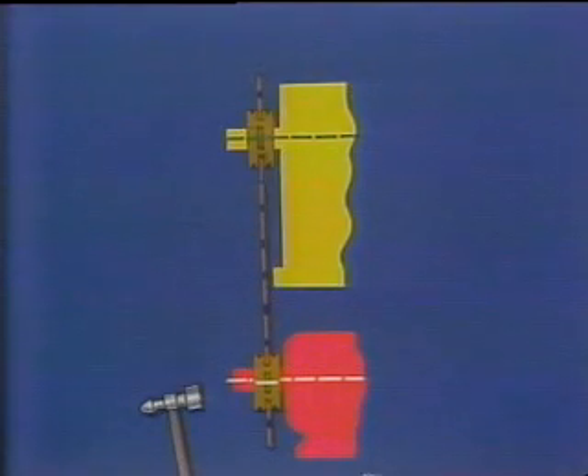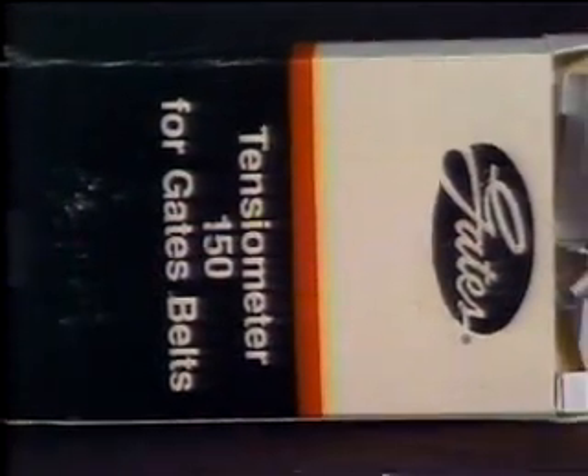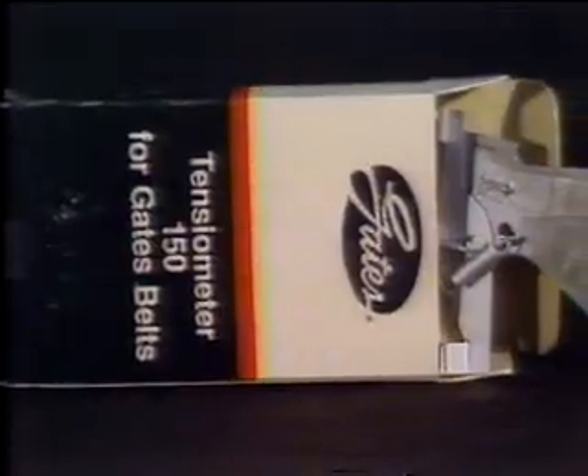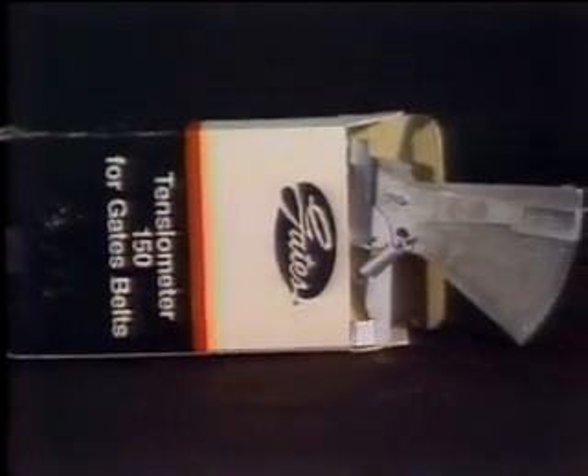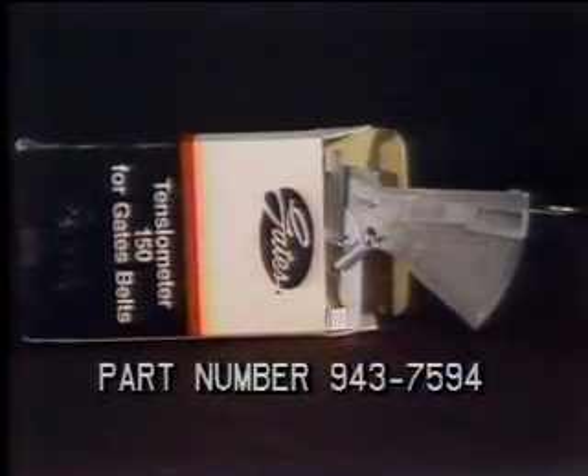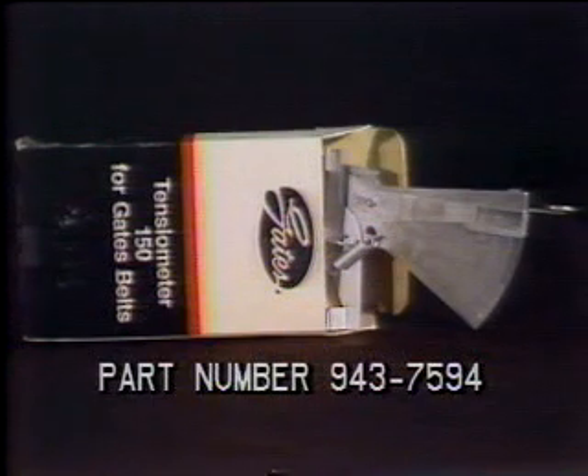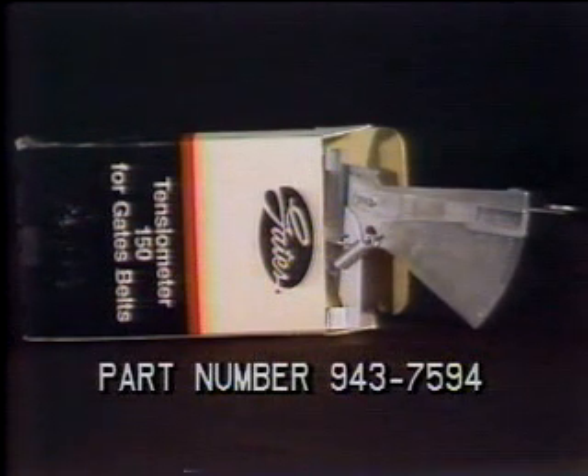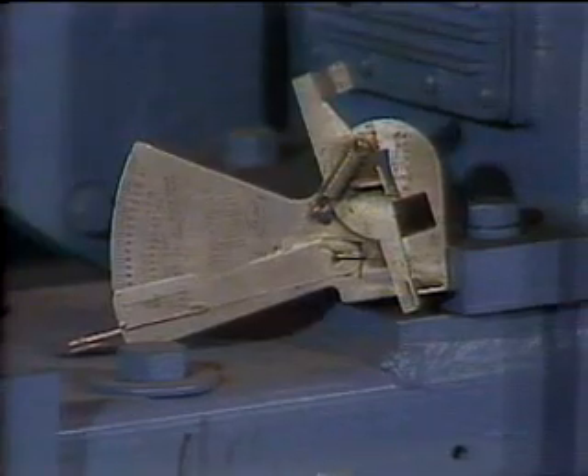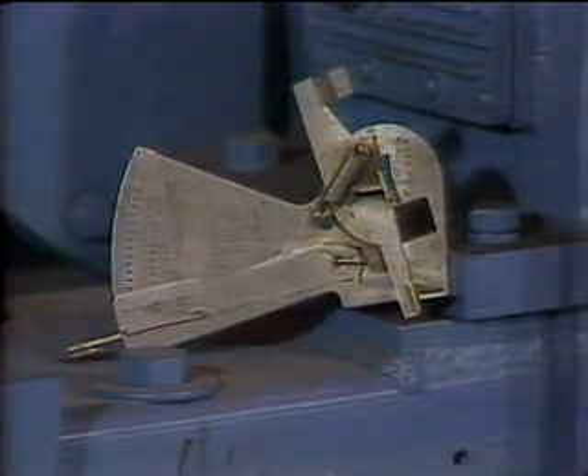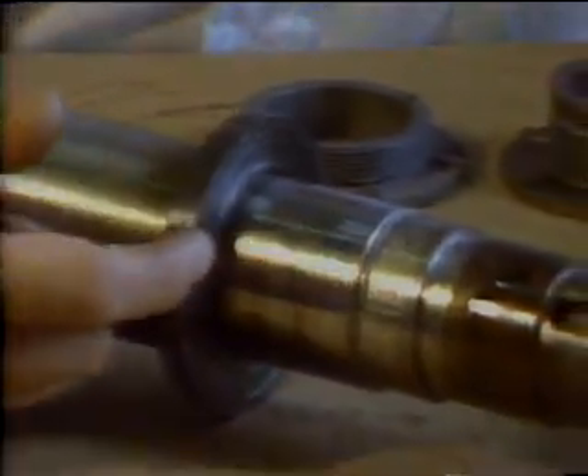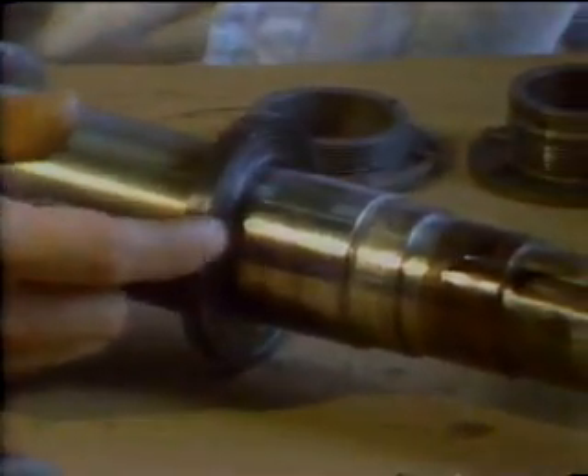Then lock it down good. Don't move the compressor sheave. We'll get into more detail on this a little later. Finally, check your belt tension to be sure that it's correct. The gauge for doing this is supplied with each Aquachem, or additional gauges can be ordered from Aquachem. It's part number 943-7594. Proper belt tension is really more important than most people realize. 50% of all the compressor damage that we've seen is caused by too tight a belt tension.